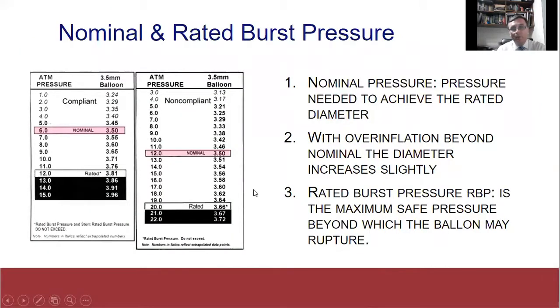What are the basics about nominal and rated burst pressure? The nominal pressure is the pressure needed to achieve the rated diameter. For example, if you have a balloon of 3.5 millimeters diameter, to reach this diameter you need to inflate it up to 6 atmospheres. With overinflation beyond the nominal, the diameter increases slightly. And when you finally reach the rated burst pressure, this is the maximum safe pressure beyond which the balloon may rupture. In this case, if you are using a 3.5 balloon and inflate up to the rated burst pressure, the diameter will increase up to 3.8 millimeters.